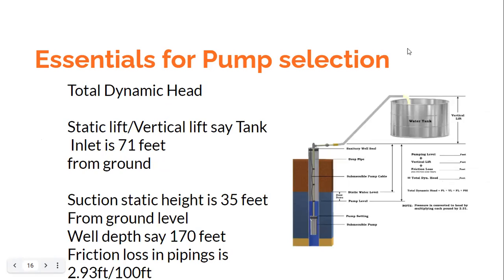For example, let us say the tank — meaning the outlet of the water in the tank — is at a height of 71 feet from the ground. That gives us the static lift or vertical lift. Now let us say the water level from the ground is about 35 feet. If you put a tape inside the well and measure where the tape touches the water level, that height is the suction static height — in this case 35 feet from ground level. Let us say the well depth is 170 feet.